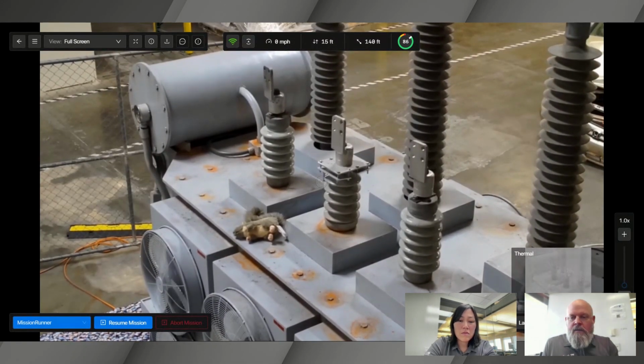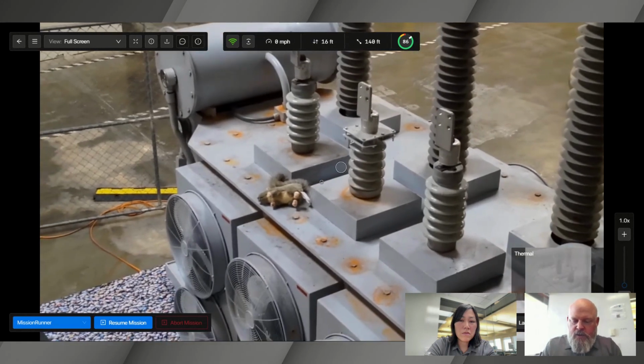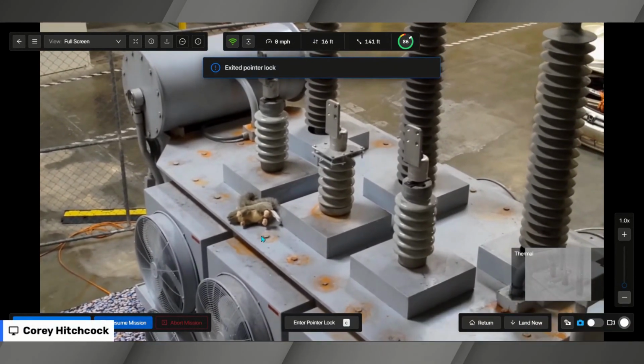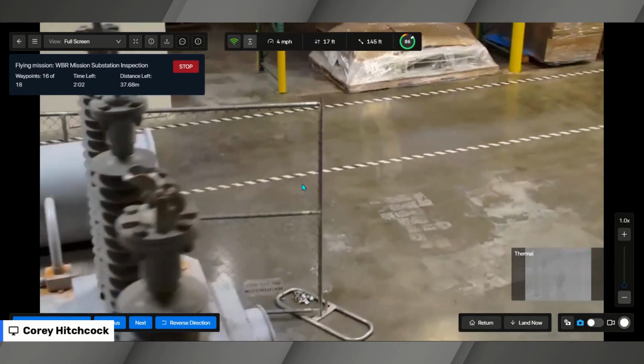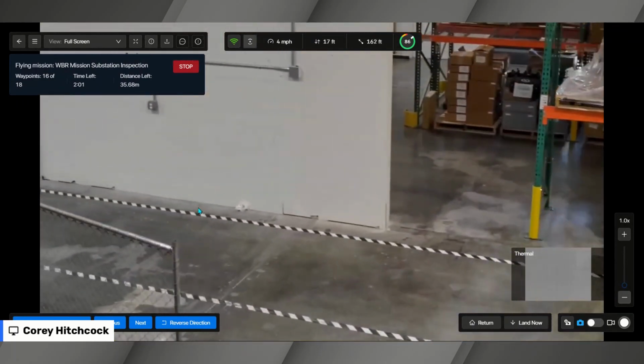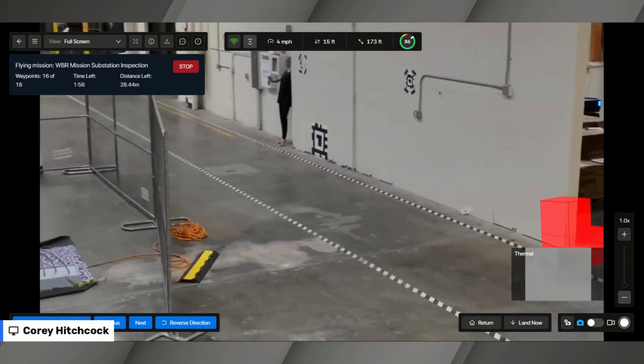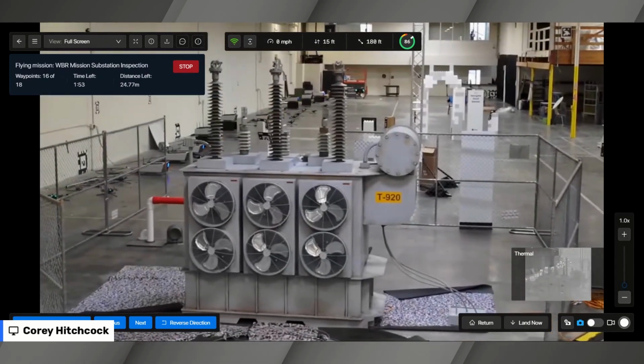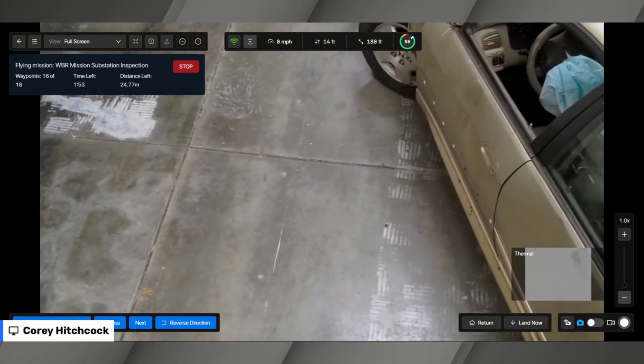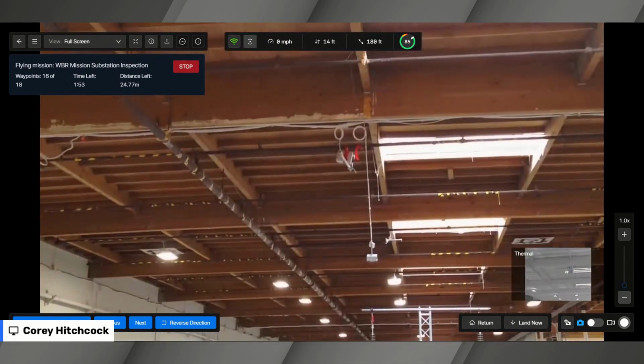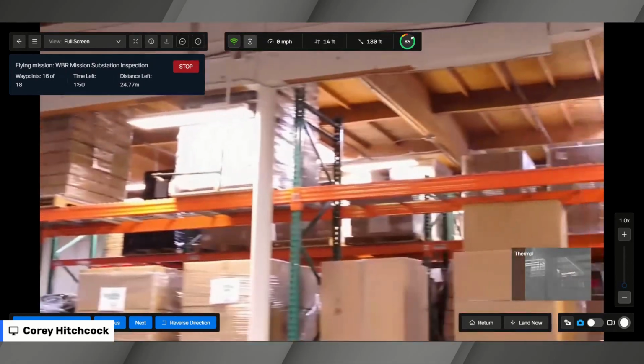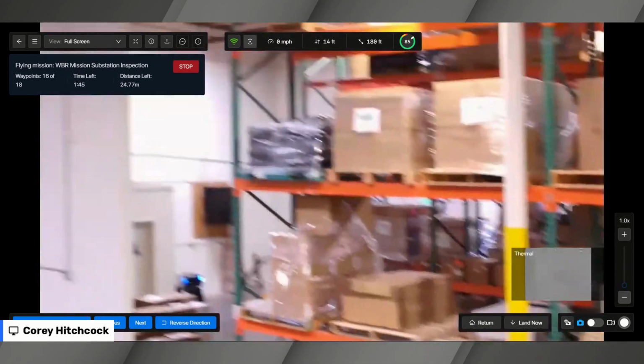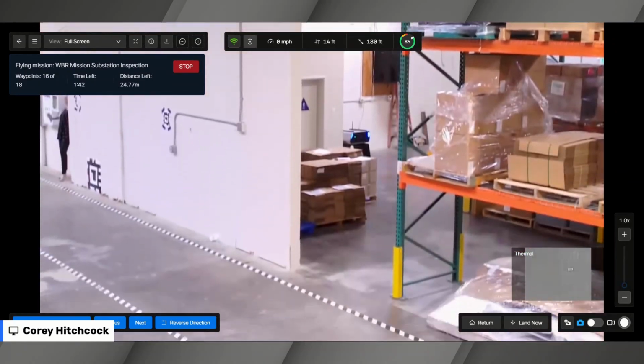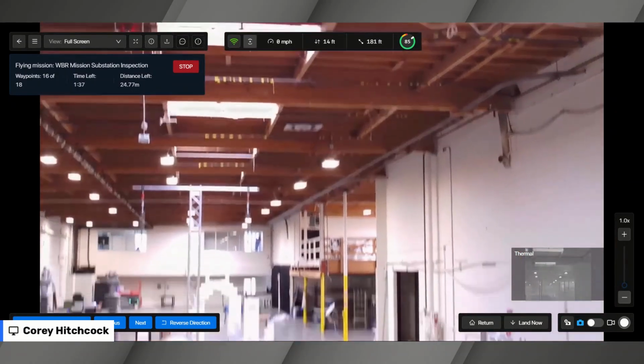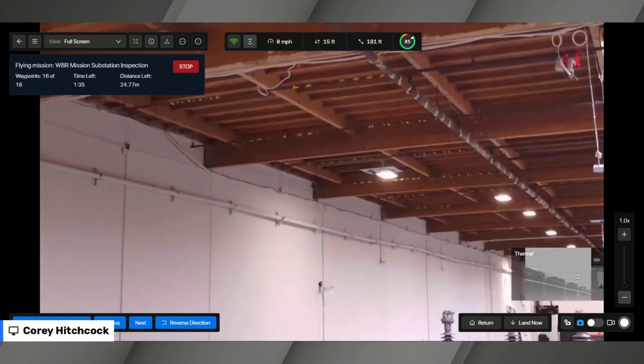I'm going to go ahead and resume this mission and continue talking. In the case of this high magnitude momentary fault, where you've got distribution automation, and out on the distribution line you have that high magnitude momentary which has locked your line out, but you can't safely re-energize that line without sending somebody to patrol it. It could be a situation where it was a lightning strike, or a tree limb fell through the primaries, or it's something that can be re-energized.